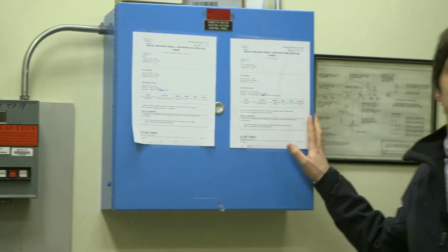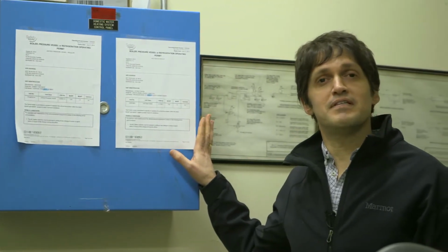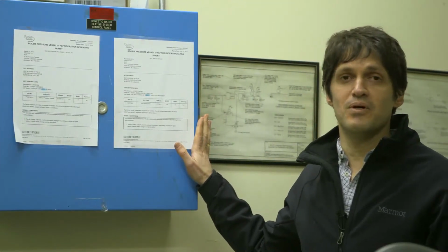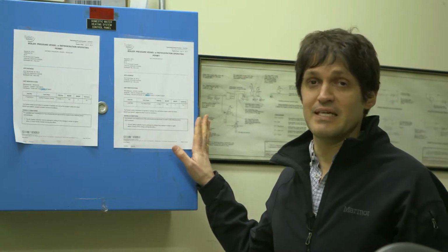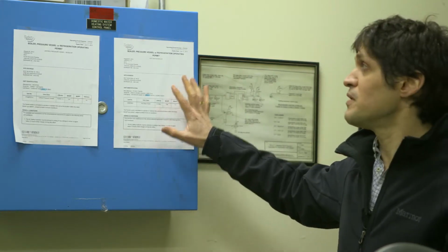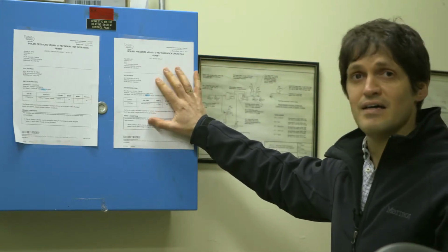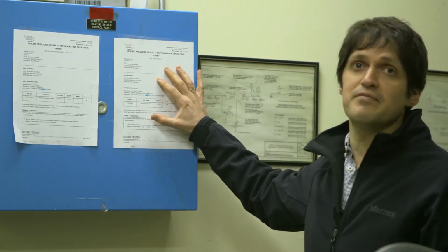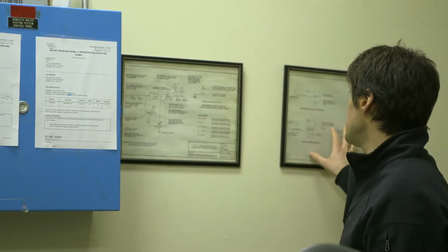A very important thing to look at when we look into a boiler is how it's controlled. Often you'll see that there's a lot of opportunity with boiler control, because if they're not controlled well, they could operate very inefficiently. So know how the boiler is controlled. In this case, look at your control panel if it exists at all, and look at control drawings that would be available typically in the mechanical room or in a boiler room.